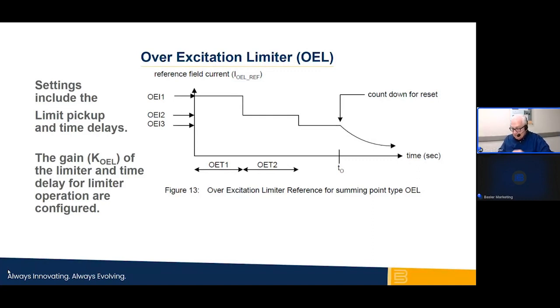That equation for the time, the numerator in that fraction, according to the standard, is 33.75, and the exponent for the current is 2. It's a square, remember, and the constant value in the binomial is 1. So it's I squared minus 1 that dictates the amount of time that condition will be tolerated, or the limiter will tolerate.